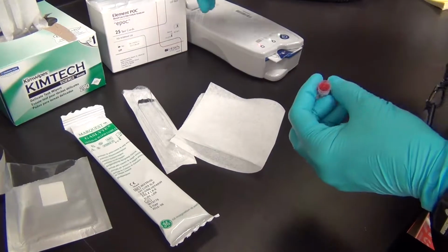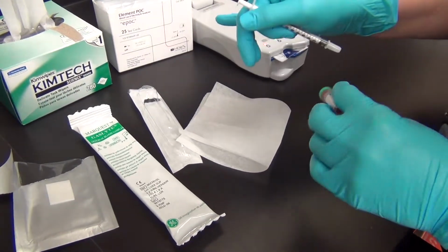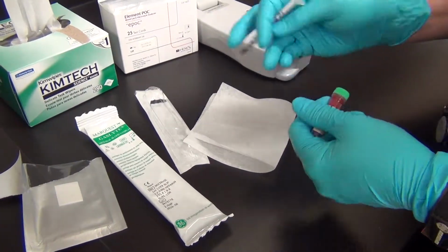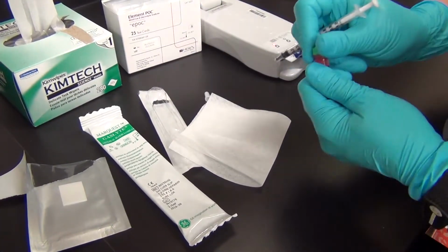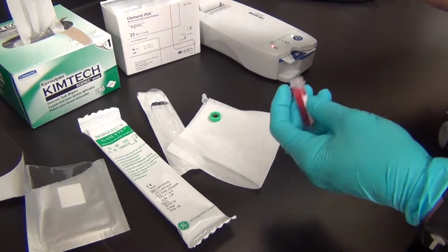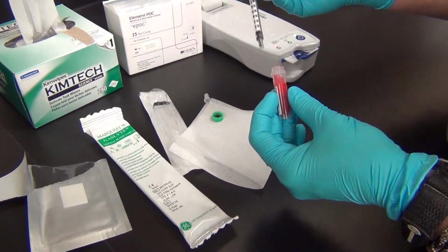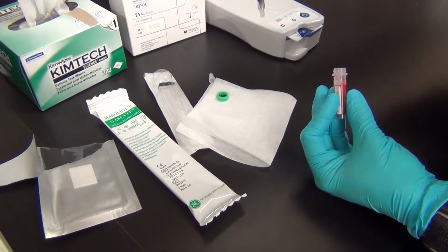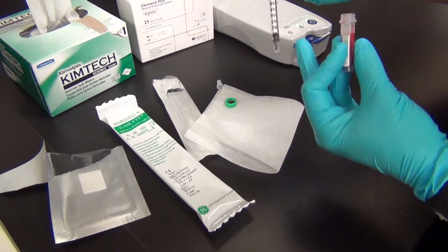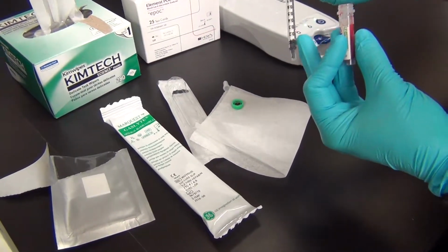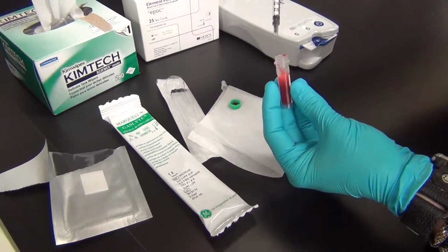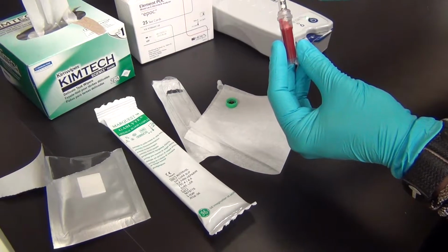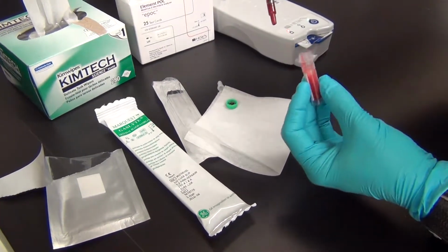As the machine is calibrating right now, the screen is telling me it's calibrating and do not inject sample. Once that 3 minutes is up, it'll beep and tell me I'm allowed to add my sample. The machine requires at least 0.1 mils of blood. What we want to be doing is loading up our syringes with probably 0.2 or 0.3 mils of our lithium heparin treated blood.